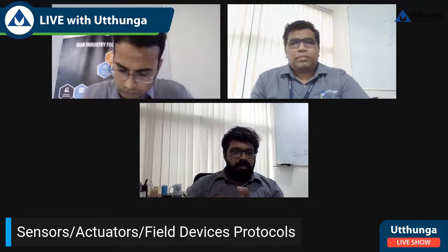And again, when you're talking about the sensors, actuators, and field device protocols, the one with the criteria, which apart from the data, power is also one important criteria here. So the popular protocol for anything on sensor actuator is HART, which is almost all the process automation or the process industry. Most of the sensors and actuators people are using HART. HART, of course, can transmit both analog and digital data by providing a field level power to the sensors or actuators from a HART master, or it could be a DCS or something like that, which is very popular in market. It's basically a two-wire communication interface.